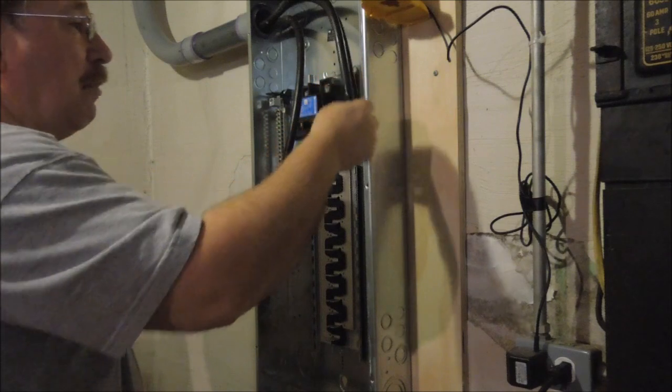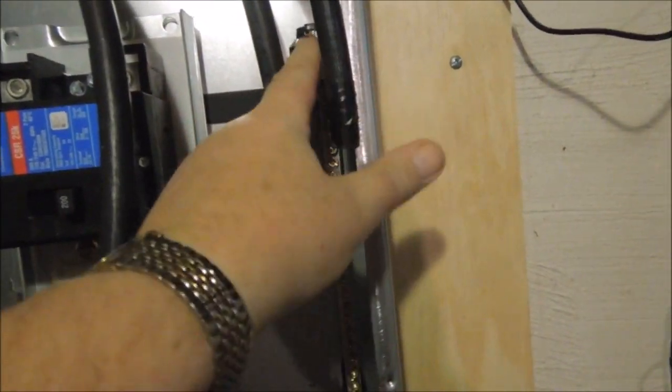This is the neutral wire. I'm going to trim that back, and these wires get trimmed back and they go into the top of the main breaker. Doesn't matter which one - probably put this one in the left one, that one in the right one. The only one I have to be sure of is that the neutral goes to the ground bar.